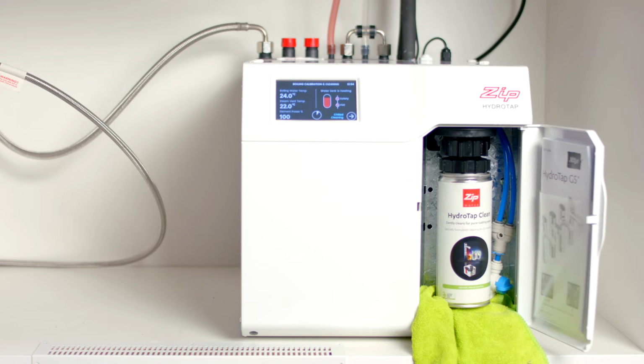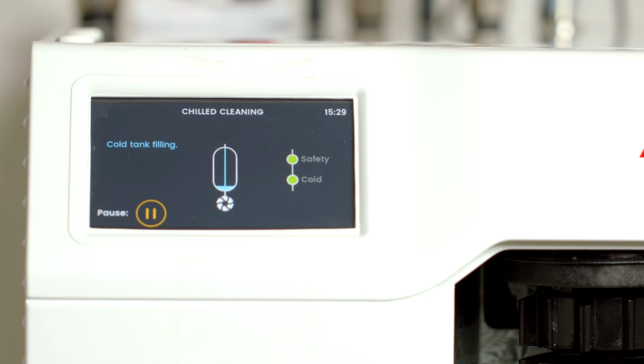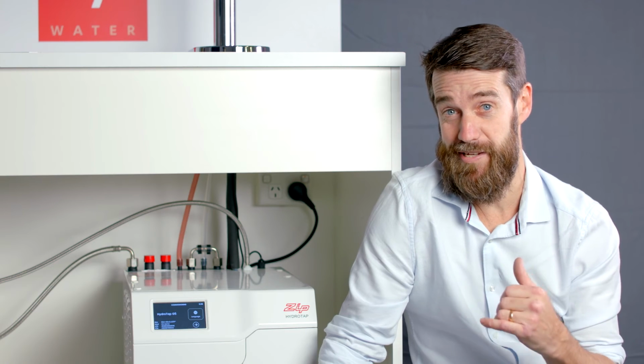Next, the HydroTap will need to calibrate. Press the play symbol to start the process. At the same time the boiling water tank is calibrating, the HydroTap Clean process will also occur. When you press the play symbol, you'll see the boiling tank commissioning screen. At the bottom of the screen, there's an arrow button to take you to the chilled cleaning screen. This will show you a picture of the tank and the solenoids inside the HydroTap. This will open and close during the process. Both the boiling calibration and HydroTap Clean processes are automated and take about 10 minutes to complete.